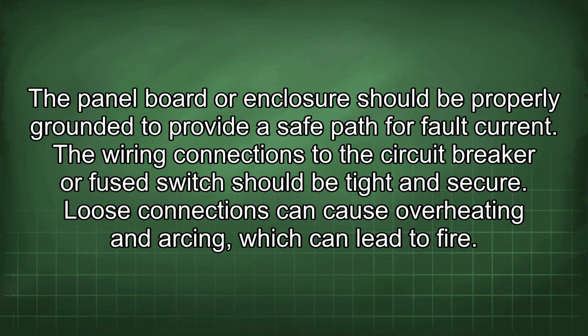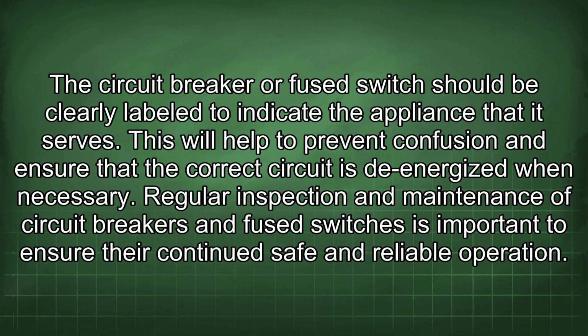The wiring connections to the circuit breaker or fuse switch should be tight and secure. Loose connections can cause overheating and arcing, which can lead to fire. The circuit breaker or fuse switch should be clearly labeled to indicate the appliance that it serves. This will help to prevent confusion and ensure that the correct circuit is de-energized when necessary.